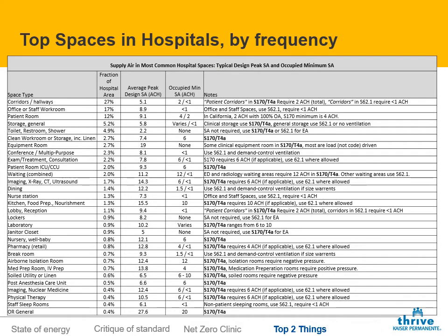And the single most common space in hospitals is corridors. We have miles and miles and miles of corridors. A quarter mile of corridor for every 100,000 square foot of hospital. And our design engineers tend to design those at an average of 5 air changes per hour. Everybody looks at that and says, wow, that's crazy. I don't know why they're doing that. But then everybody submits their plans and the numbers don't lie, man. The code minimum there is 2 air changes per hour. That's a 60% turn down opportunity.